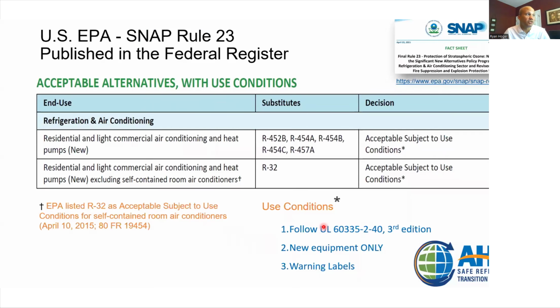This is the list of refrigerants that SNAP has for the residential HVAC equipment as well as light commercial. So basically things with scroll and rotary compressors for the most part. This is the list that the manufacturers can choose from. There are 6 refrigerants on here. All 6 of these refrigerants are in fact flammable.